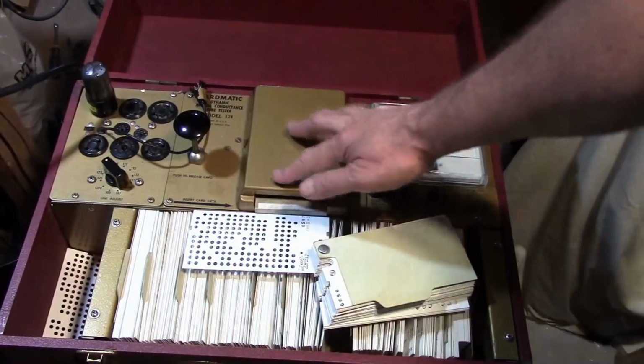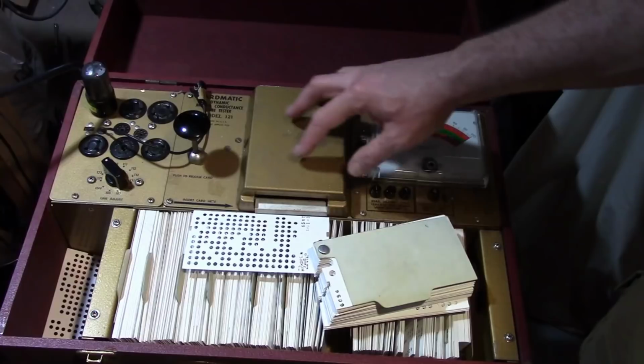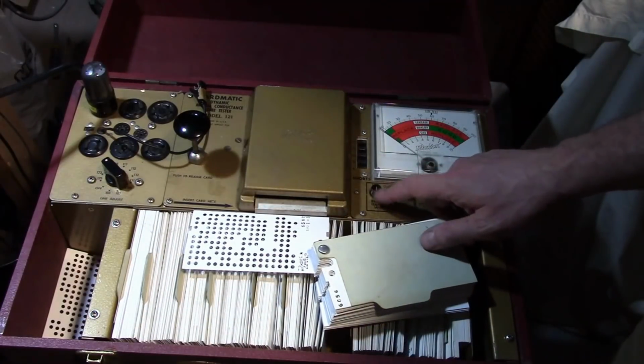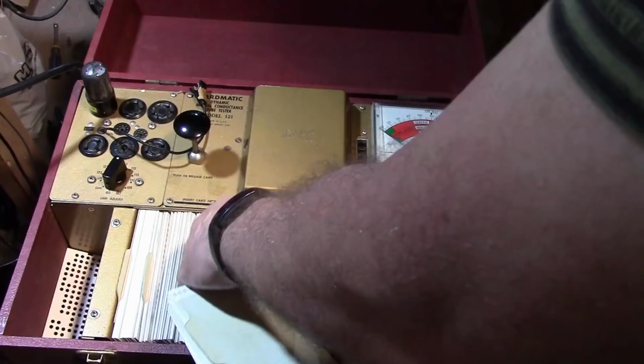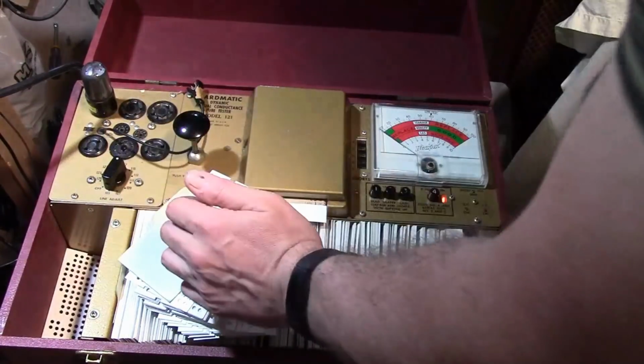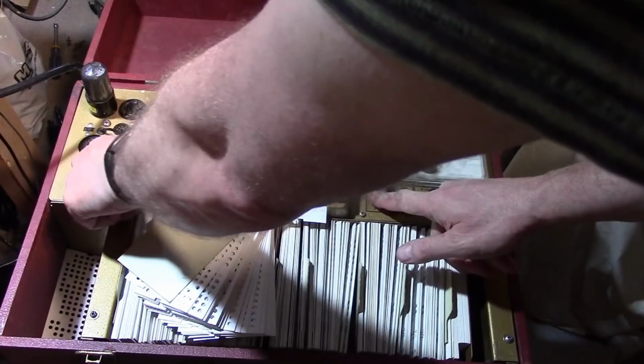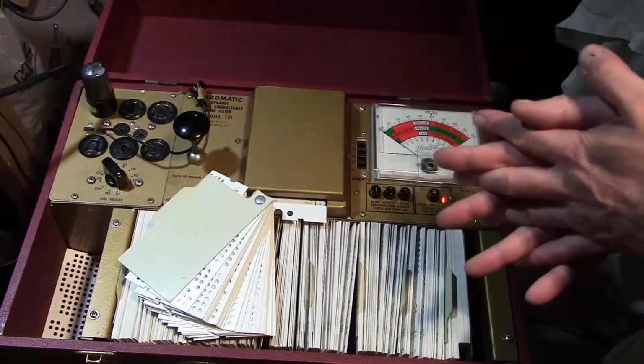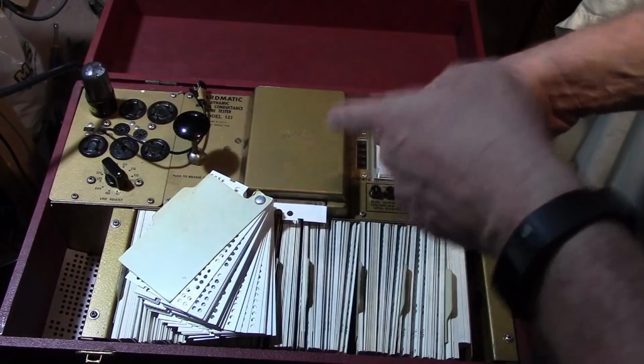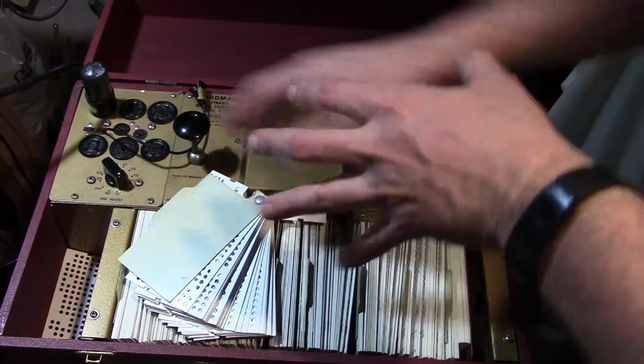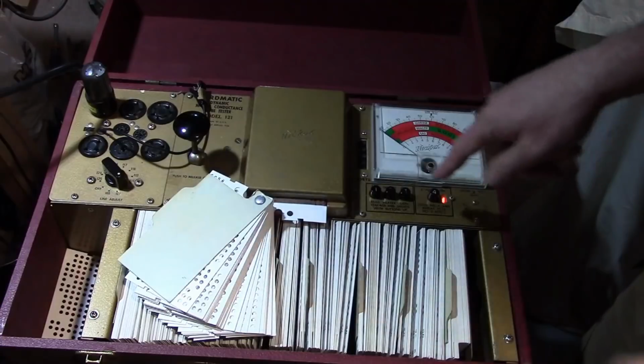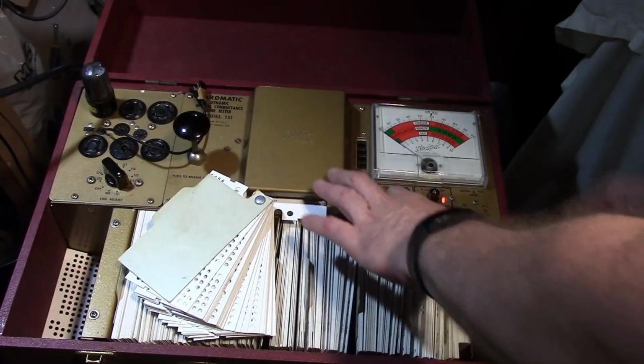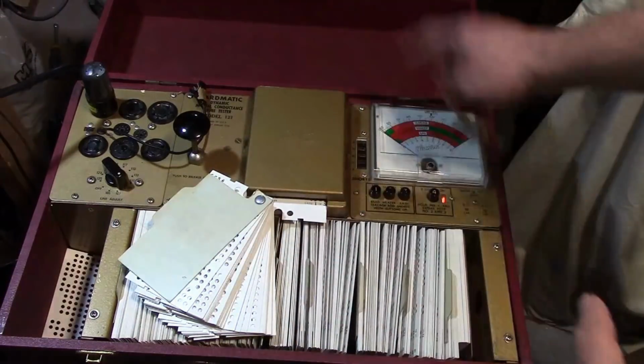So this has no tubes inside of it. There's no warm-up time. A lot of tube testers have tubes inside, and you let them heat up for a while. This does not. Let's see, until you put a card in, the thing doesn't do anything. Alright, so we do line adjust. Good. Cool thing about this is, there's two triodes in this tube. If you use a tester that has all the rotary switches on it, like a Model 600, you have to do a whole bunch of changes to do each section of the tube. With this, you just hold down a button and you can repeat the tests. And it does the shorts test automatically. You don't have to do anything. If there were any shorts, these lights would light up.